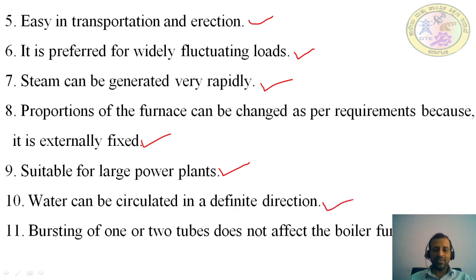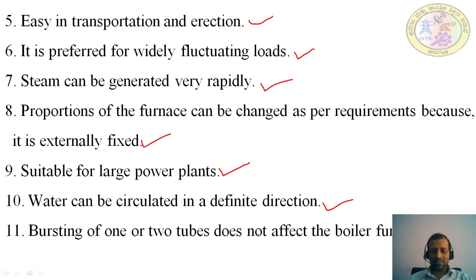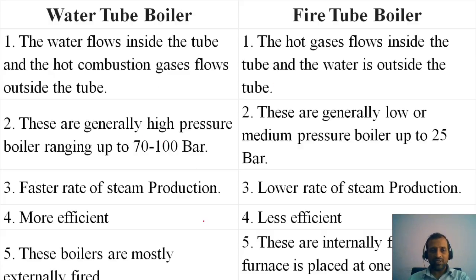Water can be circulated in a definite direction because the water tubes are fixed in a slanting position, so the flow of water is also in a particular direction. If there are parallel water tubes placed between the uptake header and downtake header, and one or two tubes burst, there is no need to stop the boiler — you can continue functioning the boiler normally.